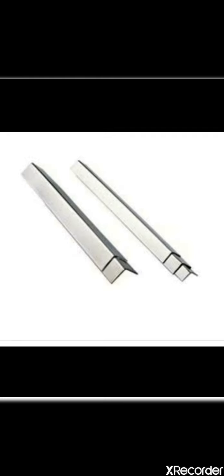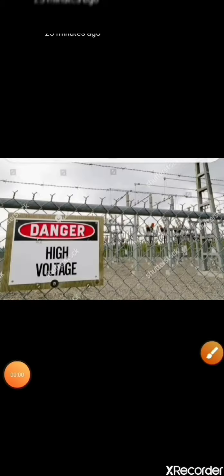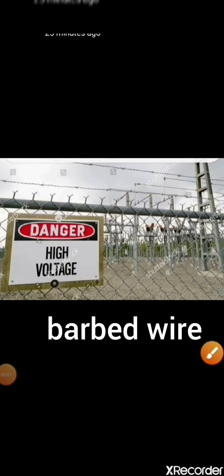Next is the MS channel. It is used to support the disc insulator and lightning arrestor. Next is the dropper angle iron. It is used to support the pin insulator. Barbed wires are used to stop climbing of unauthorized persons. So these are the barbed wire. And then this is the danger plate. The danger plate provides a visual warning on the substation and discourages public access.